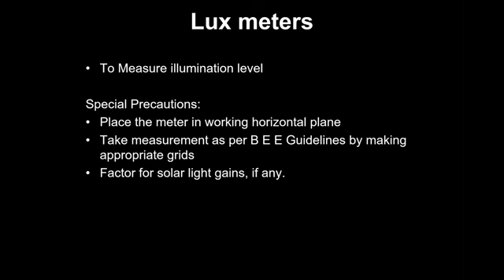But there are some small things we need to take care of: the meter should be at the working horizontal plane. It should not be taken at random locations, or at ground level or a very high level. It should be where the people are sitting and working, and take the measurement there. BEE has given a very big procedure and guidelines for doing the measurement, which need to be adhered to when you are doing it.